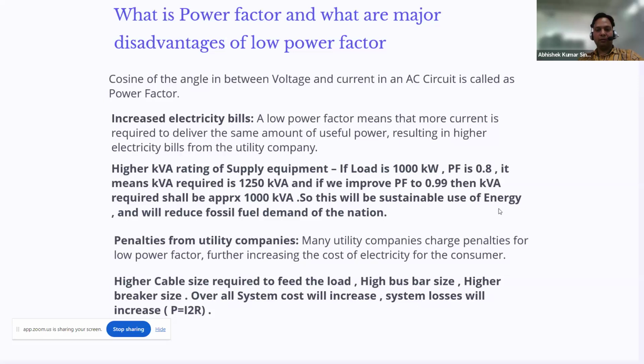So now the government is saying, if your power factor is low, then you have to pay for it, because it is increasing the capacity of the source from where the power is coming. Suppose we have a load of 1000 kilowatt and the power factor is 0.8, then the kVA required is 1250 kVA. Why? Because 1000 divided by 0.8, as you all know. And if we improve the power factor to 0.99, then the kVA required shall be approximately 1000 kVA. So this will be sustainable.